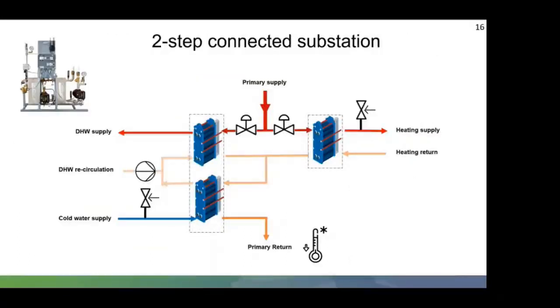Now, 2-step connected substations. This is what we would provide generally as standard. As mentioned in the previous slide, there's also another step option to design, again, to increase the use of energy efficiency and raise the comfort levels. Using a 2-step connection takes latent heat and preheats the domestic hot water. So again, in the summer, your water's coming in at a specific temperature, but in the winter, if you get a really cold winter, that water's coming in a lot colder. So your system's working a lot harder to heat the domestic hot water up to a decent level.